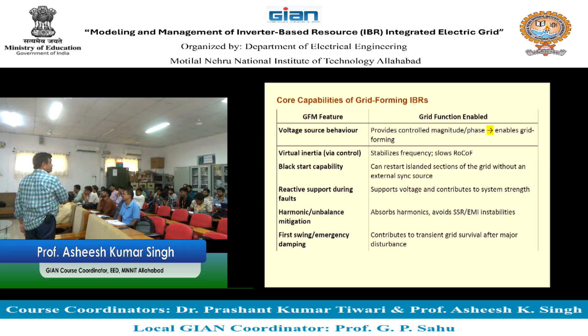So, practical challenges in implementing GFM: current limiting constraints are there, because these power electronic controls can have some current limitations. So they can typically only operate up to 110% of the rated current of the system, and sometimes fault currents are much more than this 110%, right. So that is the issue. It limits fault support and inertia injection during events.